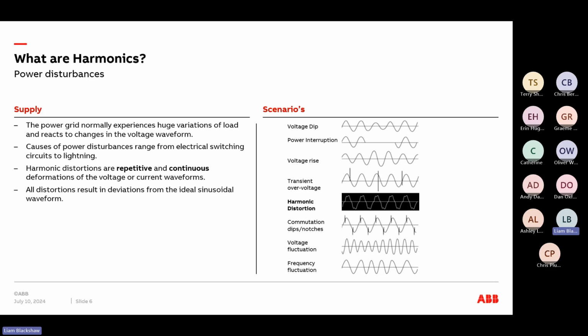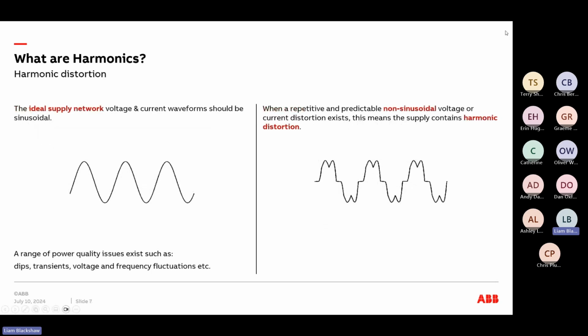All distortions result in deviations basically from that ideal sinusoidal waveform, which we put on this next slide nicely here. There we go, it's working now. So, harmonic distortion. In an ideal supply network, you want the voltage and the current waveforms to be sinusoidal, like the left-hand side of the slide here. We've touched on the range of potential power quality issues, but ideally we want that signal on the left-hand side. In reality, it's very difficult to get that in a realistic situation. So we may end up with something a little bit like what we see on the right-hand side.